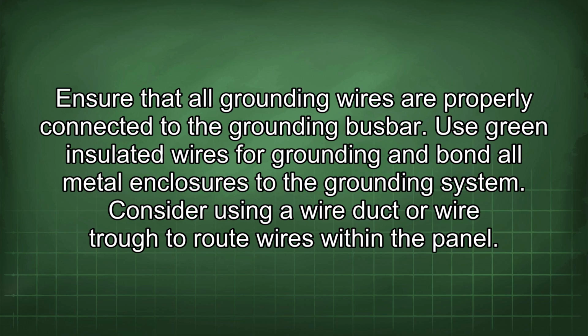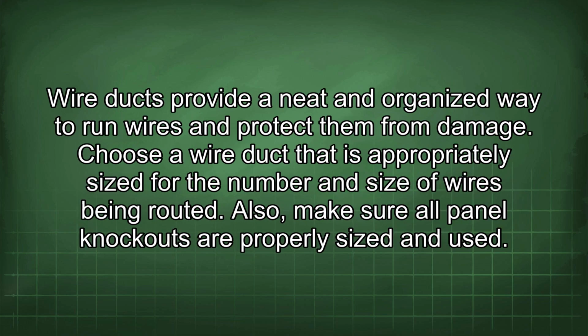Consider using a wire duct or wire trough to route wires within the panel. Wire ducts provide a neat and organized way to run wires and protect them from damage. Choose a wire duct that is appropriately sized for the number and size of wires being routed.